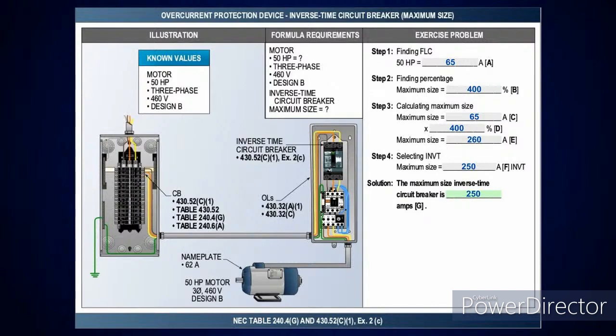Now, the only thing you have to look at here, the 400% is where the full load currents are 100 amps or less. If that horsepower motor was greater than 100 amps, you'd take it at 300%. Okay? But this one, it's less than 100, so you just take the 65 amps times 400%, it's 260 amps. The next size below that is what? A 250 amp. Now, that's not hard to follow.